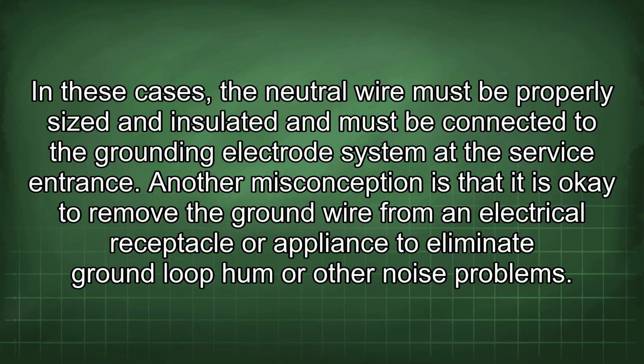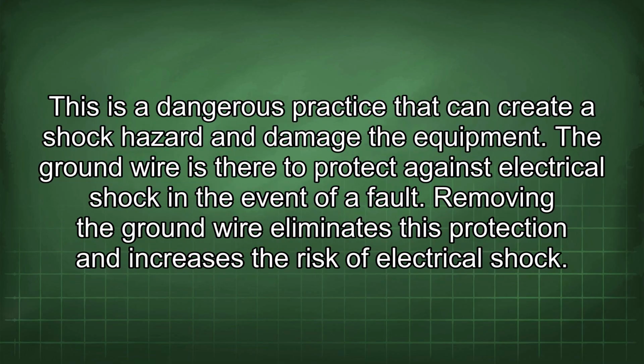Another misconception is that it is okay to remove the ground wire from an electrical receptacle or appliance to eliminate ground loop hum or other noise problems. This is a dangerous practice that can create a shock hazard and damage the equipment. The ground wire is there to protect against electrical shock in the event of a fault. Removing the ground wire eliminates this protection and increases the risk of electrical shock.